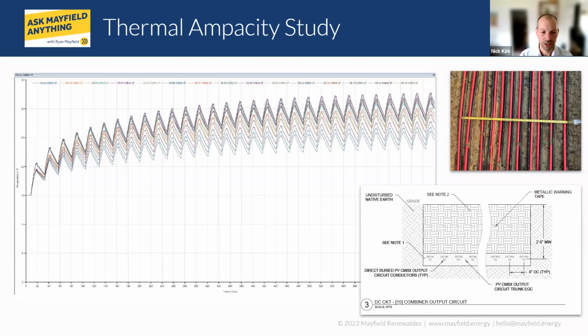This basically, during the nighttime, the soil is going to cool off, and during the daytime, the soil is going to heat up due to the loading on the conductors. And so by accounting for all this, we were able to determine that this spacing is sufficient, and our end result was a max temperature of 33 degrees C.